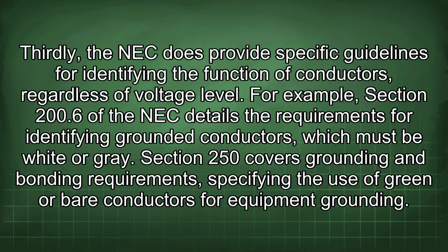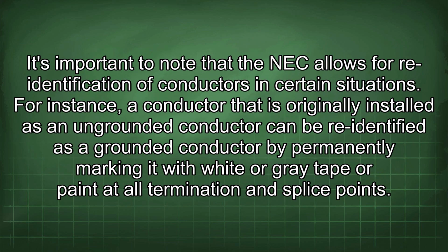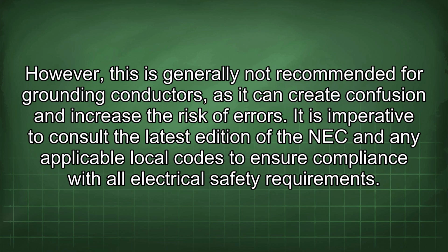Thirdly, the NEC does provide specific guidelines for identifying the function of conductors, regardless of voltage level. For example, Section 200.6 of the NEC details the requirements for identifying grounded conductors, which must be white or gray. Section 250 covers grounding and bonding requirements, specifying the use of green or bare conductors for equipment grounding. It's important to note that the NEC allows for re-identification of conductors in certain situations. For instance, a conductor that is originally installed as an ungrounded conductor can be re-identified as a grounded conductor by permanently marking it with white or gray tape or paint at all termination and splice points. However, this is generally not recommended for grounding conductors, as it can create confusion and increase the risk of errors.